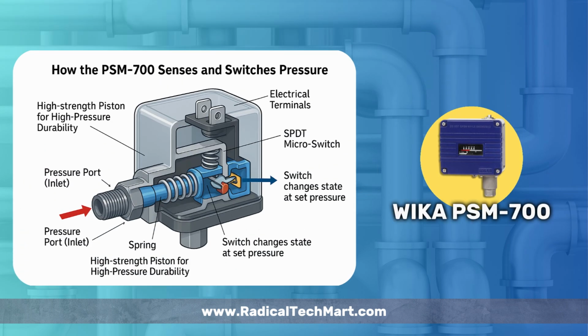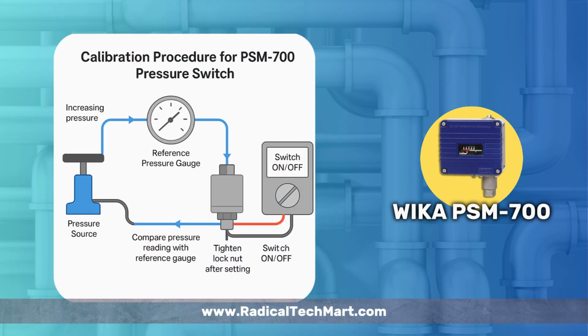Like other models, the PSM-700 also works on the diaphragm or piston principle. But here, the sensing element is reinforced with a stronger spring and piston assembly to handle higher pressures without fatigue. As system pressure increases, the piston actuates a SPDT microswitch, providing an on-off output at the set pressure. The internal mechanism ensures excellent repeatability and long life, even in continuous duty operations.